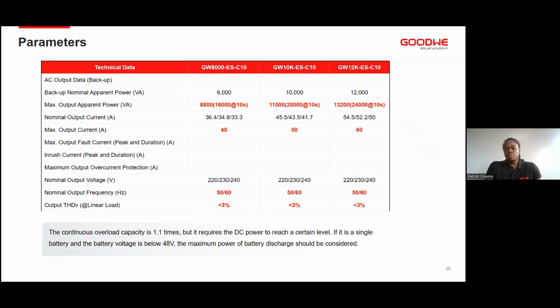The powerful backup technology used on ES Unique is quite unique. The inverter is capable of handling 2 times the nominal power for a maximum of 10 seconds during the backup state. This duration is actually important and works fine for inductive loads, for their startup time, for the inrush current. This feature allows you a full house backup capability because it supplies high current and stable frequency with less than 3% harmonic distortion on your AC lines. So it's quite unique.